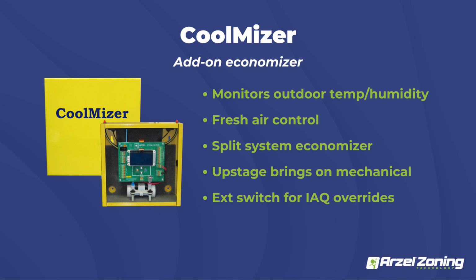So also really nice because you don't need any enthalpy controls or any external devices. It's going to ship with just an outdoor temperature sensor that's going to read outdoor temperature and humidity. And then it's going to provide lockouts for either economizer function, but it also incorporates fresh air function as well. So it has a secondary port on the top where you're able to introduce fresh air to that system based on outdoor temperature and humidity. So it'll either do a combination of the economizer with fresh air, or you can use one or the other. So it's really up to you guys how you want to utilize this panel.